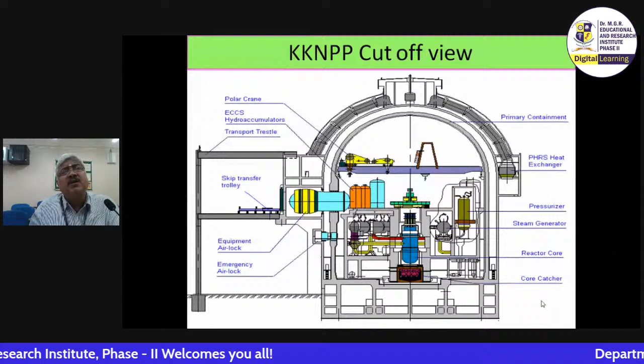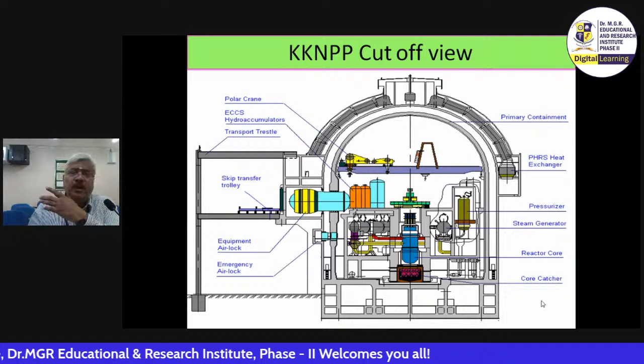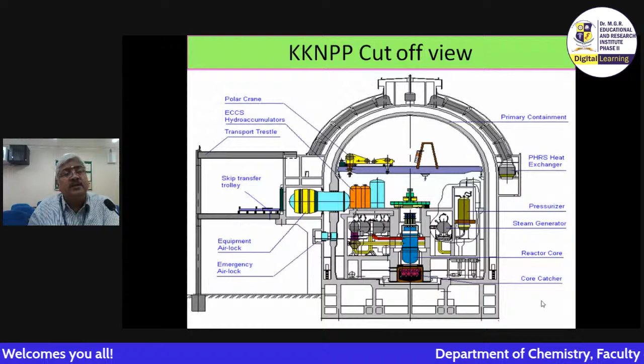Next is the passive heat removal system, PHRS. This system actuates during beyond design basis accidents, such as a station blackout condition, when everything else is gone. At that time we have to reduce the heat of the RPV. So from the SG, there is a point that goes to the PHRS. There, natural air cools the PHRS heat, and the hot air rises to the top, and then the steam goes back to the steam generator.